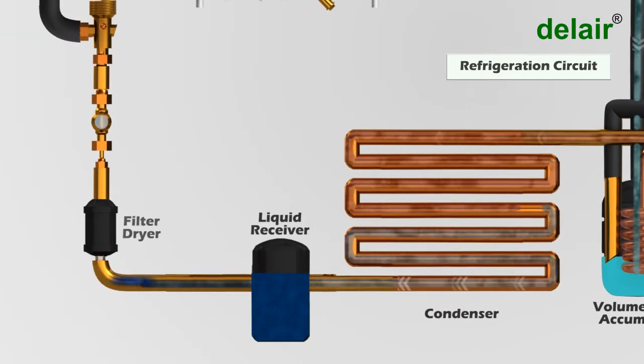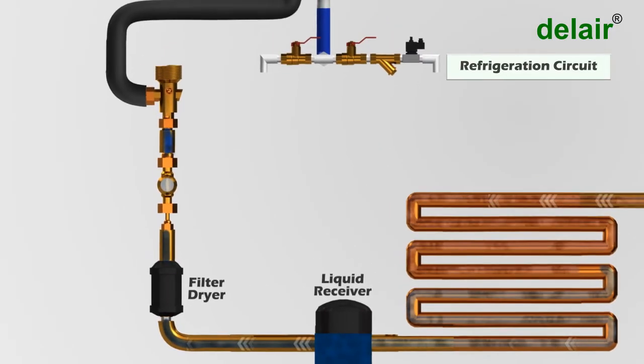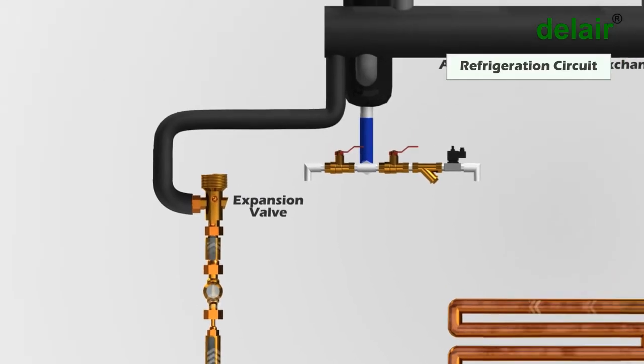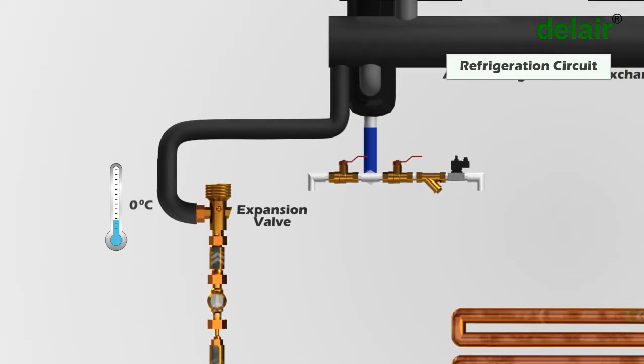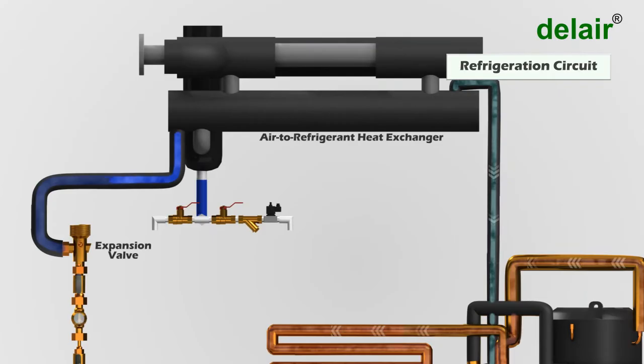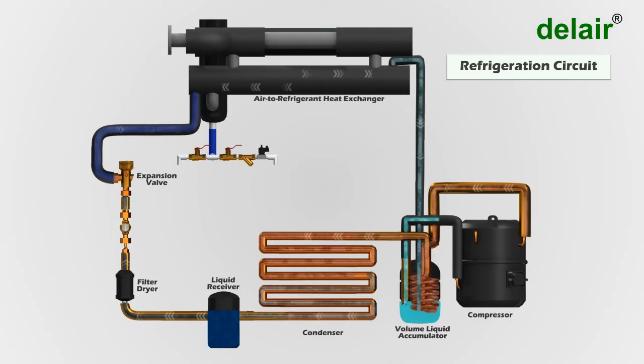The liquid then travels through a filter where impurities are absorbed. The liquid refrigerant then passes through an expansion valve which reduces the pressure, leading to a reduction in its temperature down to zero degrees Celsius. This enters into the air-to-refrigerant heat exchanger and the heat from the hot compressed air is absorbed by the cold refrigerant. This refrigerant is then sucked by the compressor and the cycle starts over again.